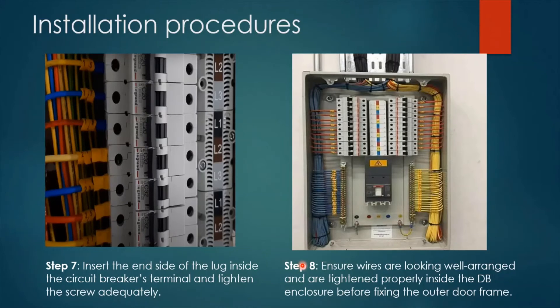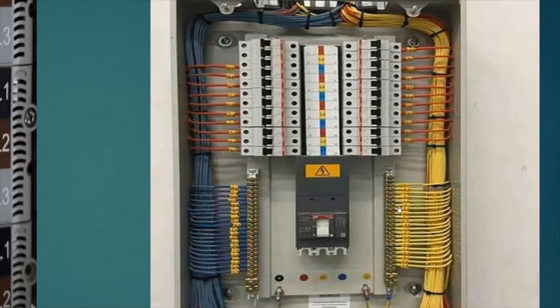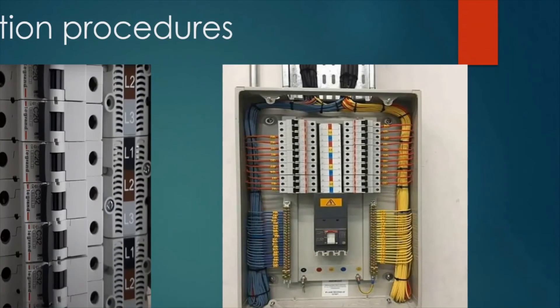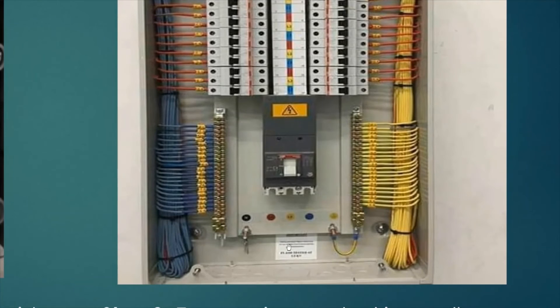Step eight is to ensure wires are neatly arranged and tightened properly inside the distribution board enclosure before fixing or installing the outer door frame. As you can see, the yellow and green wires representing the earthing wires are all terminated at the earthing terminal, and the neutral wires are terminated at the other side. Different colored wires for the circuit breakers go to different circuit numbers. The incomer can be terminated from the upper side or through an opening at the bottom side of the DB enclosure, which is more suitable.